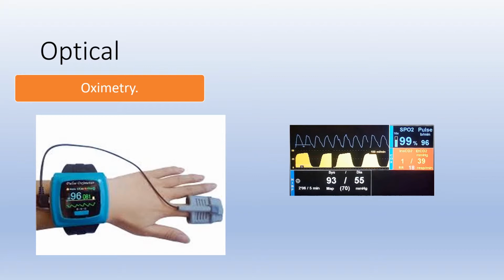Optical fibers help in a case such as having an MRI because physiological monitoring during an MRI is necessary to ensure the safety of patients when they are sedated, anesthetized, or unstable. It helps in the case that no metal should be on the body when an MRI is taking place. It also does not emit any noise.